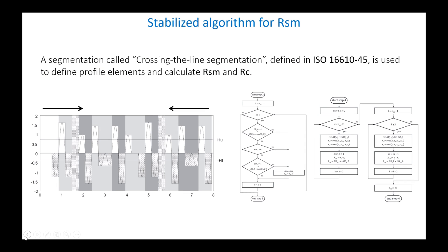The RSM parameter has undergone several updates over time in order to correct its instability and uncertainty in its definition, which made its implementation variable among different manufacturers. The new segmentation procedure, described in ISO 16610-45 and called Crossing the Line Segmentation, aims to clarify and stabilize the determination of profile elements and therefore their quantification.